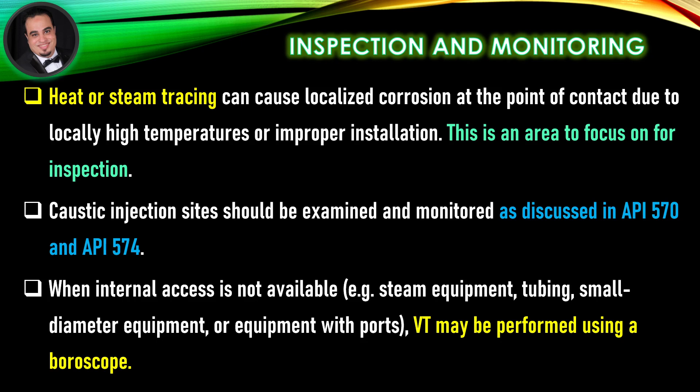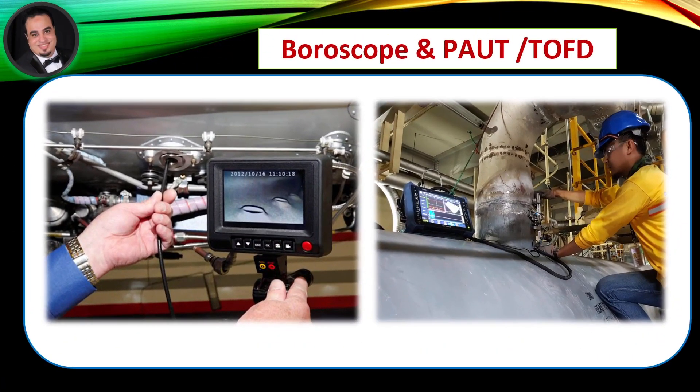Caustic injection sites should be examined and monitored as discussed in API 570 and API 574. When internal access is not available — for example, steam equipment, tubing, small diameter equipment, or equipment with ports — visual inspection (VT) may be performed using a boroscope. As illustrated in figures, examples of boroscope and PAUT/TOFD inspection are shown.